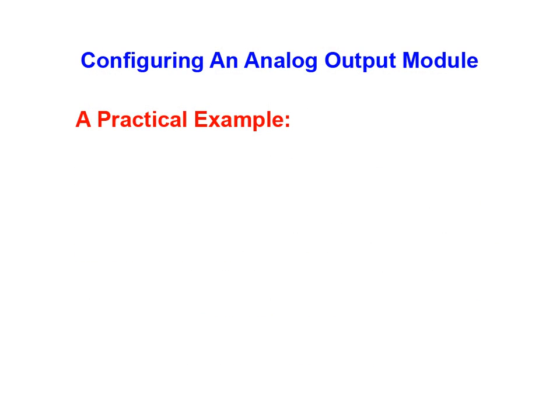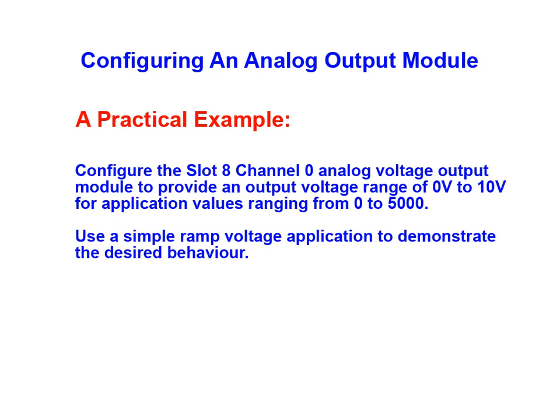We'll now move on and use a practical example to illustrate how the I/O is configured. We will configure the slot 8 channel 0 analog voltage output module to provide an output voltage range of 0 to 10 volts when values ranging from 0 to 5000 are sent to it. We will use a simple ramp voltage application to demonstrate the desired behavior.